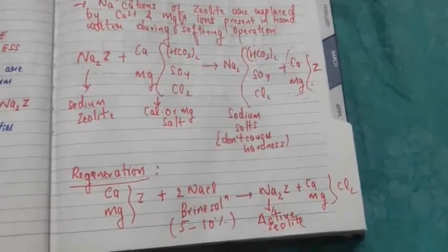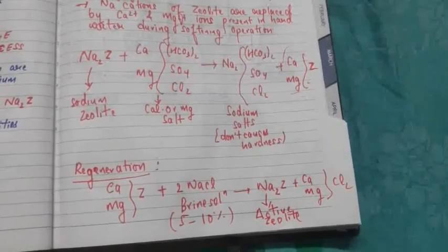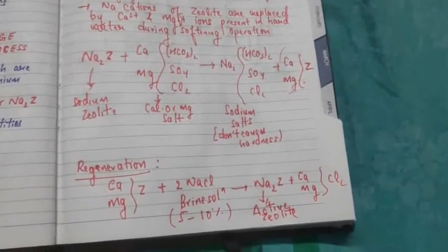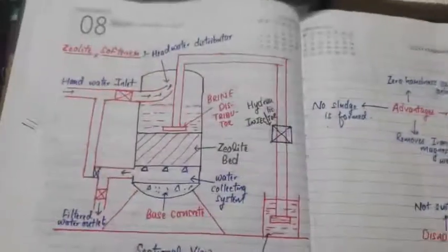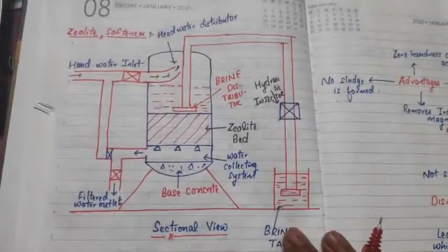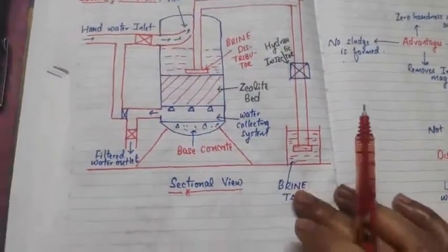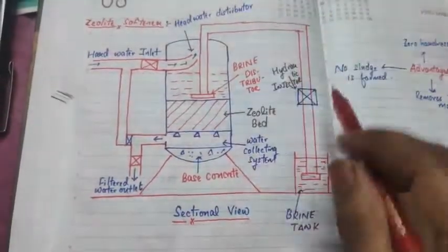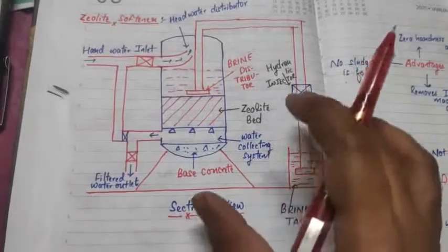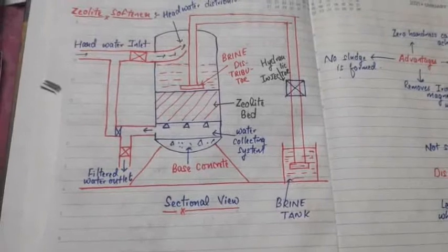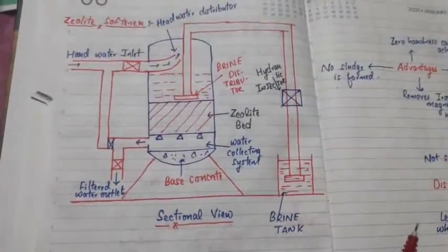A special equipment called the zeolite softener is used for this process. The zeolite softener, also called a cation exchange unit, is shown here as a sectional view. This is a pressure-type zeolite softener, meaning water enters under pressure. Two types exist: gravity type and pressure type.